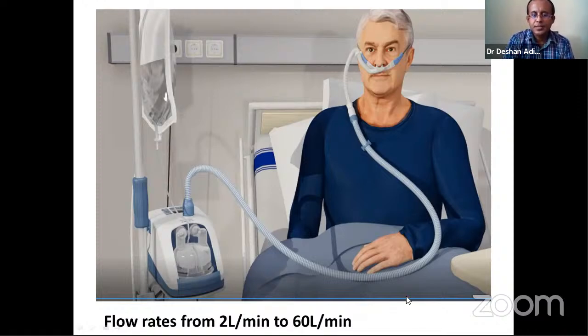It is then delivered through a specialized tubing system, which is heated so that the water does not condense at the patient interface. There are patient interfaces depending on the size of the patient: pediatric, adult and neonatal. The flow rates range from 2 liters to 60 liters per minute.